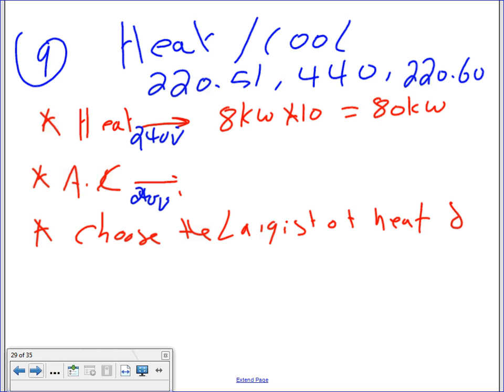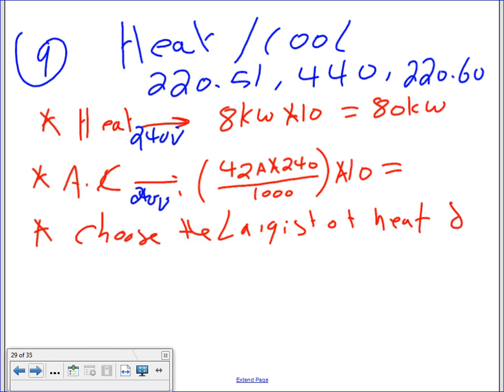That's my heat. My cool, my AC, did we give the amps for the AC? The AC amps are given at 240. How much? 42, yeah. For the AC units, I have 42 amps, multiplied by 240, divided by 1,000 because we're going to convert it into kVA. That's the kVA of one AC unit. Don't forget to multiply this by 10 so you get the 10 of them. That will get you a healthy 100.8 kVA.